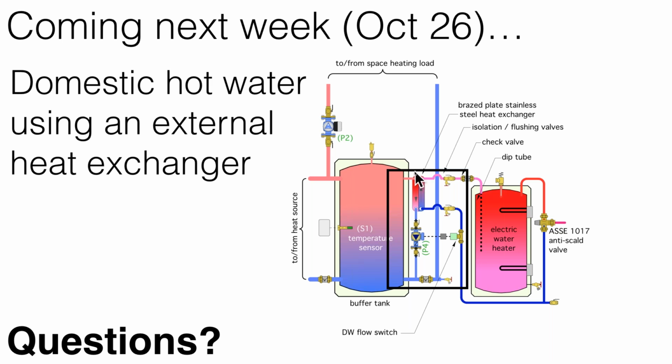Yeah, you could. The basic idea would be don't heat the buffer tank any warmer than necessary for whatever the conditions are. So I could see you configuring an indoor reset control and simply maintaining a buffer tank based on the feedback from the interior space temperature. I don't have experience in doing that, but I don't see any reason why it couldn't be done. I'm not sure which would be better for you. I suppose the indoor one does account for things like solar gain and other internal heat gains, and might give you a slightly lower water temperature requirement.